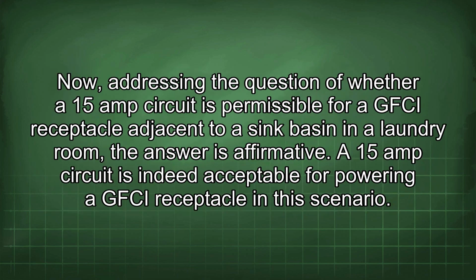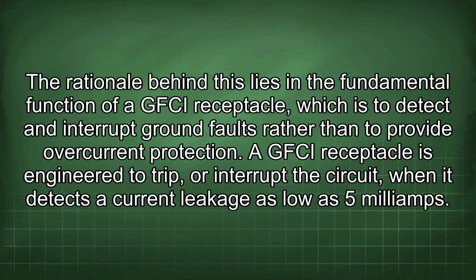Now, addressing the question of whether a 15-amp circuit is permissible for a GFCI receptacle adjacent to a sink basin in a laundry room, the answer is affirmative. A 15-amp circuit is indeed acceptable for powering a GFCI receptacle in this scenario. The rationale behind this lies in the fundamental function of a GFCI receptacle, which is to detect and interrupt ground faults rather than to provide overcurrent protection.